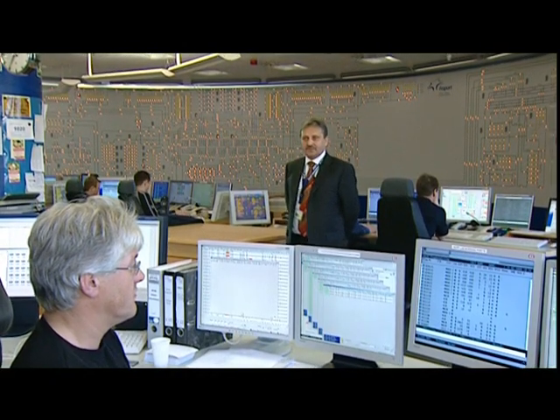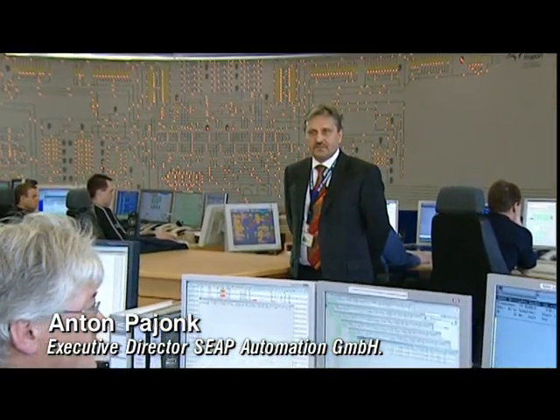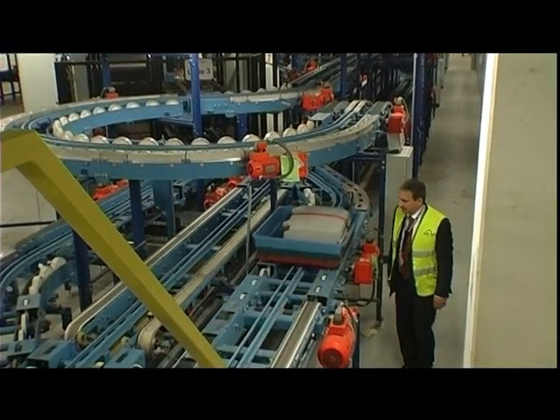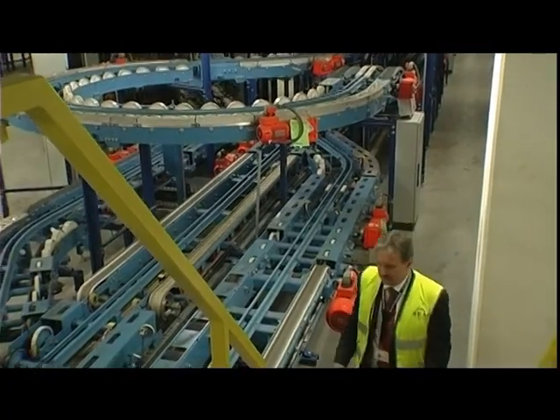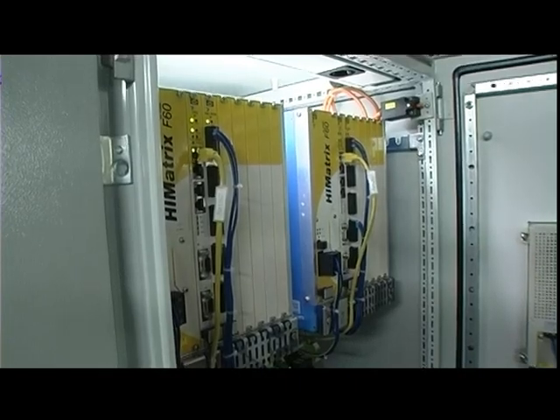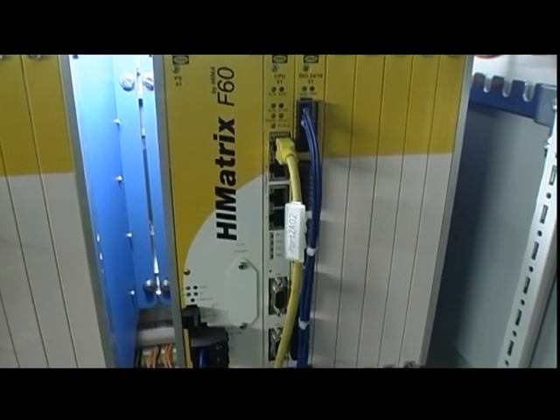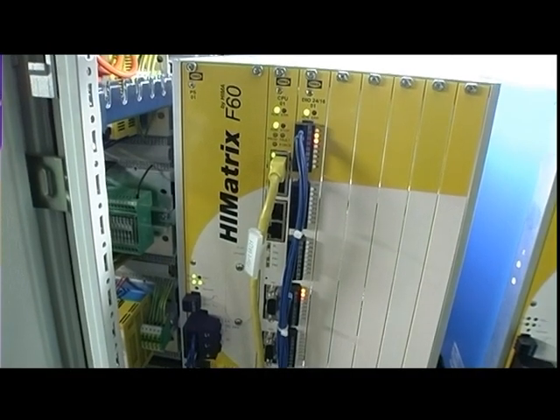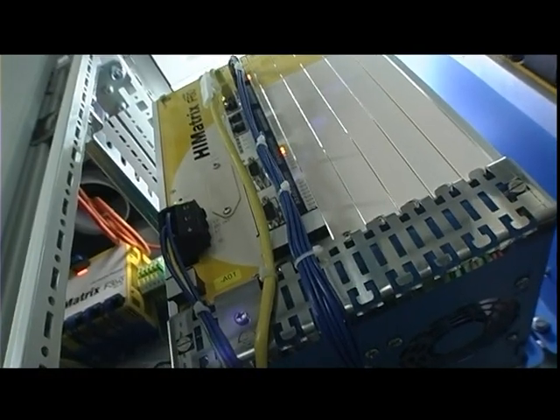My name is Anton Pajonk. I am the managing director of SEAB Automation GmbH in Langen. At Frankfurt Airport, I am responsible for updating the baggage handling system. When an emergency stop is activated, a message is received, processed and passed to the HIMatrix systems. The system is designed with redundancies: a second safety PLC in hot standby ensures full redundancy so that if a central safety PLC fails, the system switches automatically to the second one.